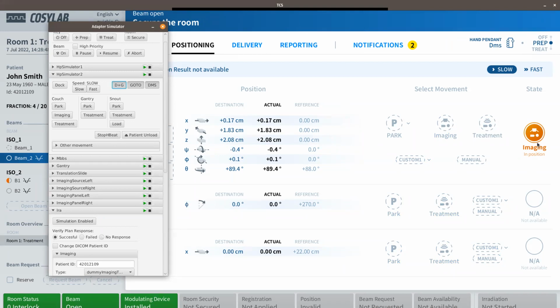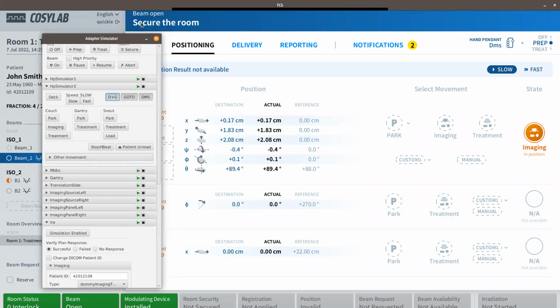So now you can see that the couch successfully moved to the inside of the imaging position. That is usually, for example, inside of the CT scanner. Movement was of course very quick because we used simulator. Usually it takes longer. And now we are ready to. Okay. Now we follow instructions. So the TCS suggests us to secure the room. So at this point, we will perform CT imaging, and at this point it is recommended that nobody is in the facility that is not supposed to be there.